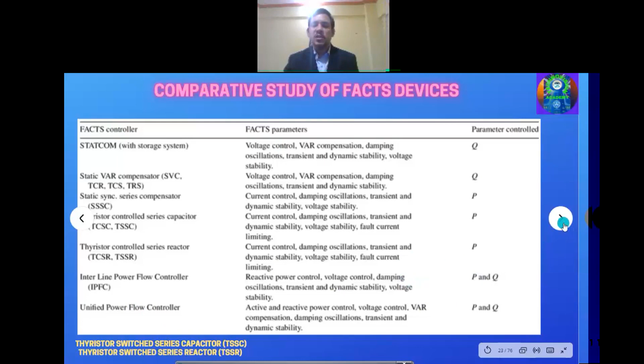Now we'll see about series compensation. We know that in series, generally the current is constant, but you can vary the voltage. You can add voltage into this line, so that ultimately you are improving the voltage profile of that line. By variable impedance such as capacitor, reactor, controlled by power electronic devices, we can overcome the subsynchronous harmonic frequencies by using series compensation.